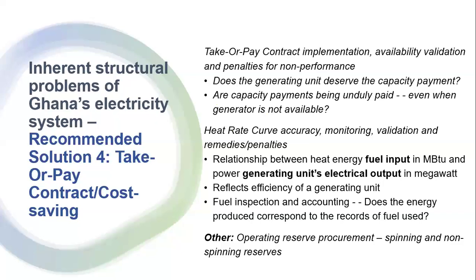If I certify a generator for spinning capacity payment, it means that unit is certified to be online, and if the grid calls that unit and says 'I want you to dispatch to 20 megawatts in the next 10 minutes for one hour,' within 10 minutes a spinning generator should be able to come online and deliver that 20 megawatts for the time requested.